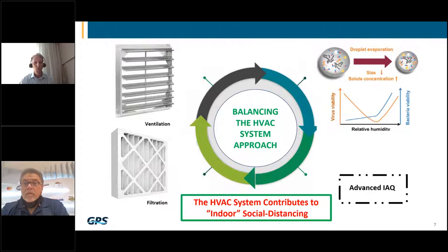The cornerstone of any good HVAC system begins with ventilation — the amount of outdoor air that I bring into a space to help dilute the pollutants of concern. Ventilation also includes the number of air exchanges provided to flush the space of contaminants. Then we have filtration — the MERV efficiency of the filter installed in the HVAC system to extract contaminants based on their size. Ventilation and filtration is the backbone of any good HVAC system.